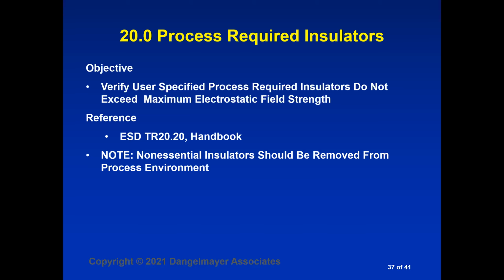Oh, and Diana was highlighting, I think she means in relationship to drag chains, especially concerning in areas that don't have conductive floors throughout the facility. Yes, of course, drag chains wouldn't work very well there. Those are the cases where you need to have some kind of ground cord on your mobile cart so that you can connect it to ground when it gets where it's going.